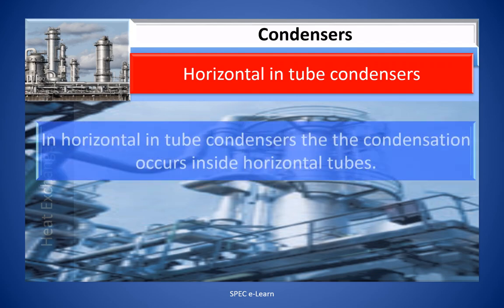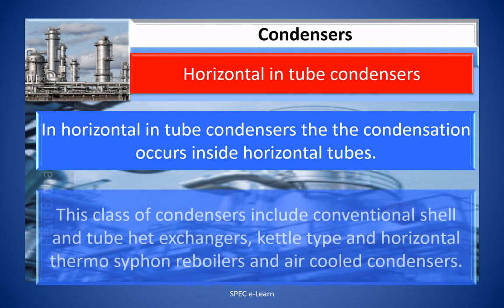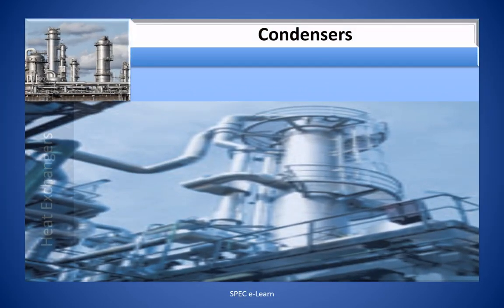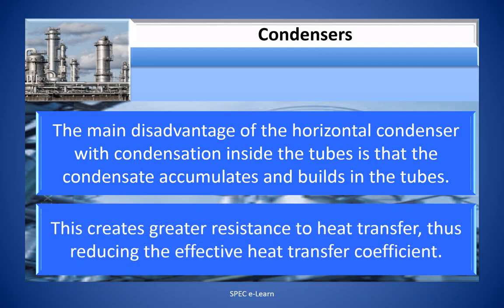In horizontal in-tube condensers, the condensation occurs inside horizontal tubes. This class of condensers includes conventional shell and tube heat exchangers, kettle type and horizontal thermosyphon reboilers, and air-cooled condensers. The main disadvantage is that condensate accumulates and builds up in the tubes, creating greater resistance to heat transfer and thus reducing the effective heat transfer coefficient.